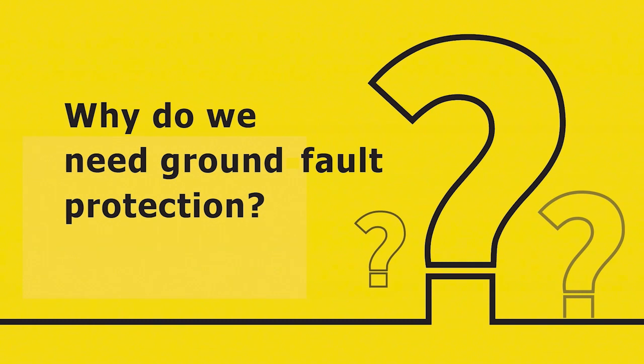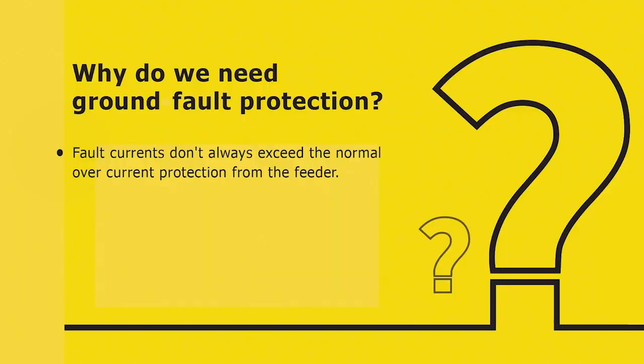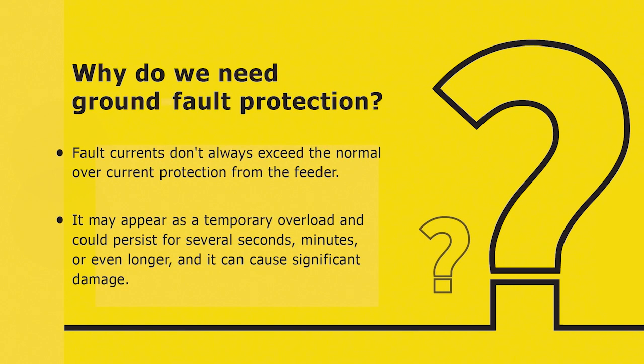So why is it that you need ground fault protection in the first place? Well, when you have a fault from phase to ground, those fault currents oftentimes will not exceed the normal overcurrent protection from the feeder itself. And so you're going to be below the trip ranges of circuit breakers and fuses, and you can get a continuous fault that's going to generate a lot of heat. And that's why we want to sense that fault and clear it. It may appear as a temporary overload, and it could persist for several seconds, minutes, or even longer. And it can cause significant damage, heating, fire, and it can really be a bad thing.